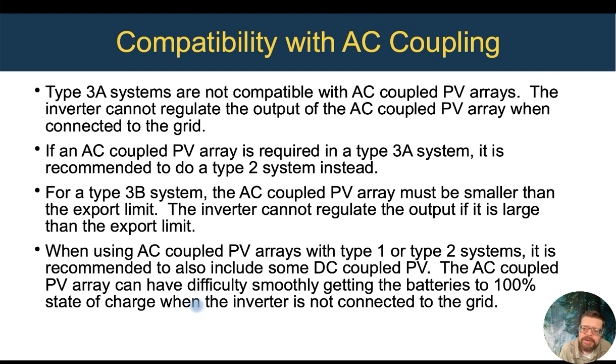When we're doing AC coupled PV arrays with off-grid systems, I always recommend also including some DC coupled PV array, and that's because it's really difficult sometimes to get the batteries up to 100% with an AC coupled PV array, because you need to very smoothly throttle that array back to just the right amount to finish charging those batteries to 100%. And usually that doesn't work. It depends on details of the exact inverter you've got on the AC coupled PV array and how that interacts with our inverter and the frequency shifting.